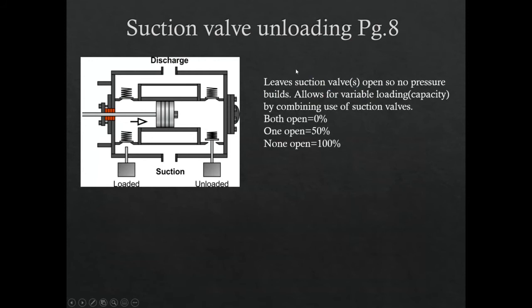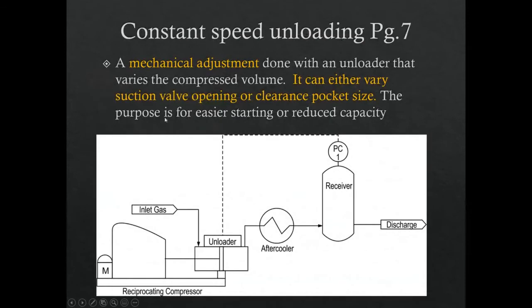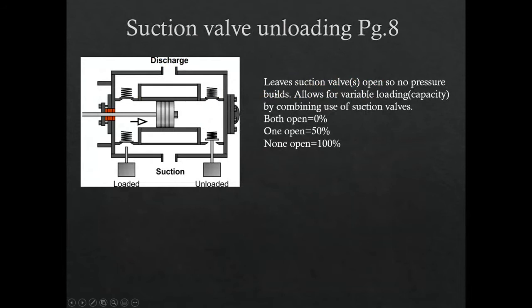Okay, so suction valve unloading. We're talking about either the suction valve opening or the clearance pocket size here. Suction valve unloading basically leaves the suction valves open so no pressure builds. This allows for variable loading by combining the use of the suction valves. So if I have my suction valves here, I can open them or close them as we want.